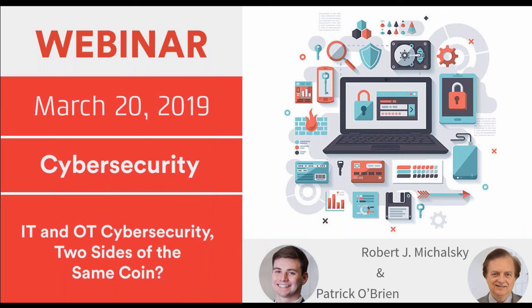And that same concept also applies to the combination between IEC 61508 and 62443. I believe it's specifically called out as performing a vulnerability assessment and having an understanding of the potential cyber threats to that device. I will definitely defer to some of my colleagues on the certification side at exida to provide a more in-depth answer. But my understanding is that performing that cybersecurity analysis, and understanding those potential vulnerabilities and issues, is now required for functional safety certification.